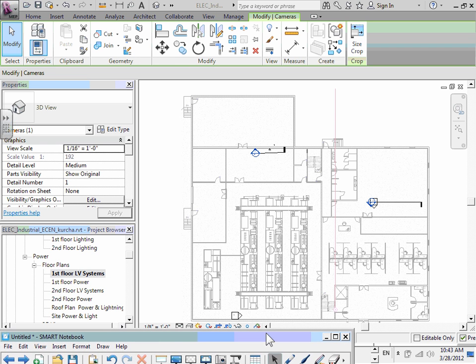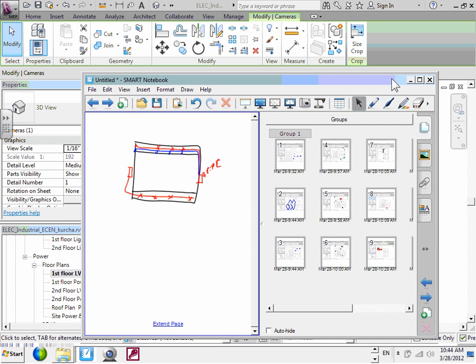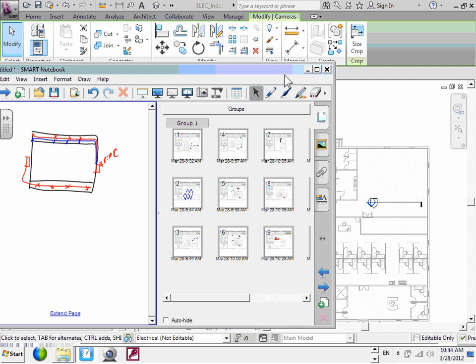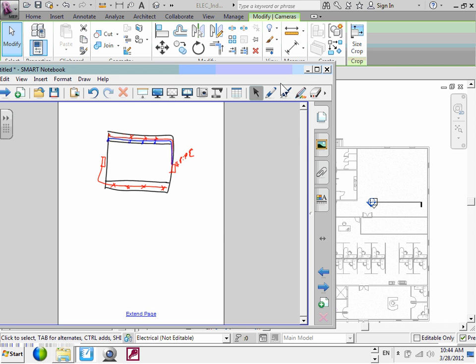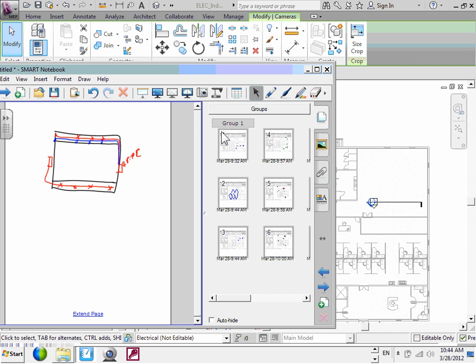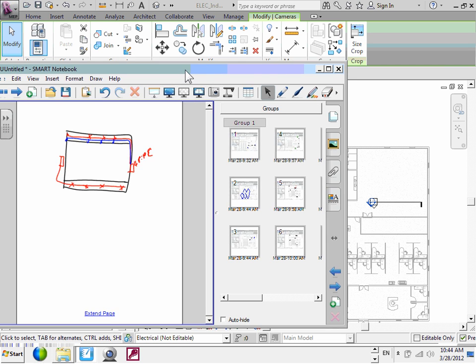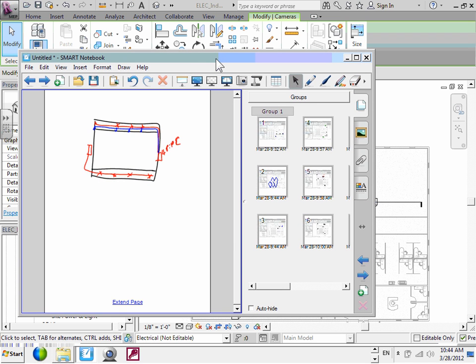And then you also have the electrical inspection. Yep, for the wiring to do. Yep. Typically, the fire marshal will do the inspection, all of our testing and inspections. So when it comes to electrical, when we have our rough-in and everything in, they'll just wait till the end because it's a low voltage system, typically 24 volts. So they don't need to see that there's no loose wire nuts, it's all in conduit and junction boxes and everything.